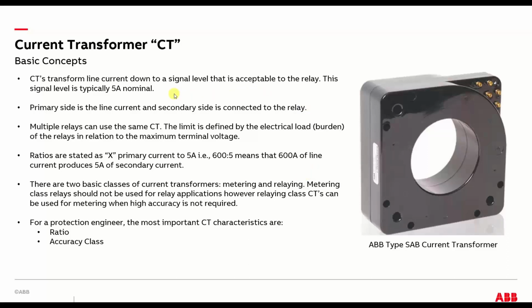Let's see here. We talked about this. The typical secondary is a 5 amp. The primary side is the one that's connected to the actual cable or circuit. The secondary side is connected to the relay. This is an interesting point. Multiple relays can use the same CT. So you can have one CT drive a couple different protective relays plus a meter.